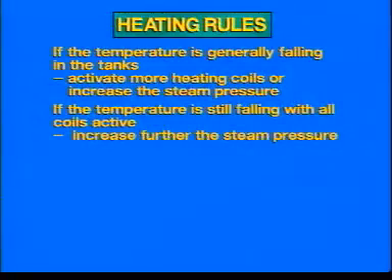If the temperature is generally falling in the tanks, activate more heating coils or increase the steam pressure. If the temperature is still falling with all coils active, increase further the steam pressure.